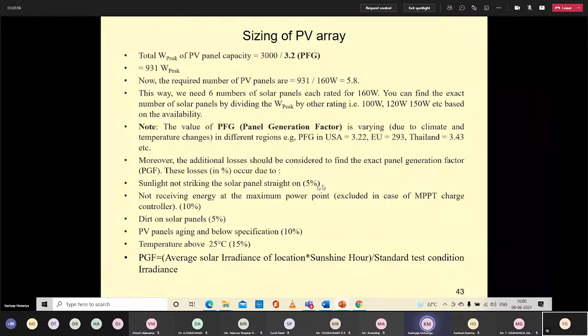Sunlight not striking the solar panel straight, consider it at 5% or whatever the variable parameter is. Not receiving energy at maximum power point, this will be excluded in case of an MPPT charge controller, but it will come into play when PWM control is there. Dirt on the solar panel is 5%, PV panel aging and below specification is 10%, and temperature above 25°C is 15%.